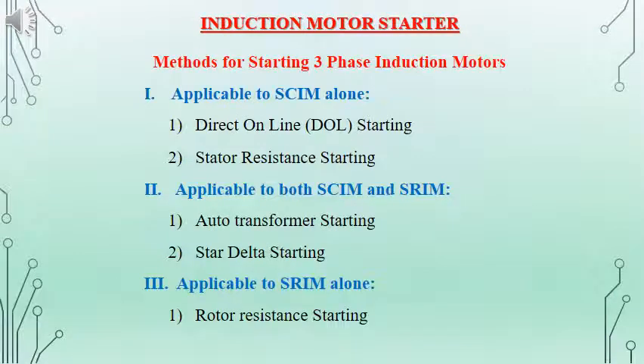There are different methods that are used for starting a three-phase induction motor. If it is the case of squirrel cage induction motor, we can go for direct online starting or stator resistance starting. For both squirrel cage induction motor and slip ring induction motor, it can be auto transformer starting or star delta starting. In the case of slip ring induction motor alone, we can go for rotor resistance starting.